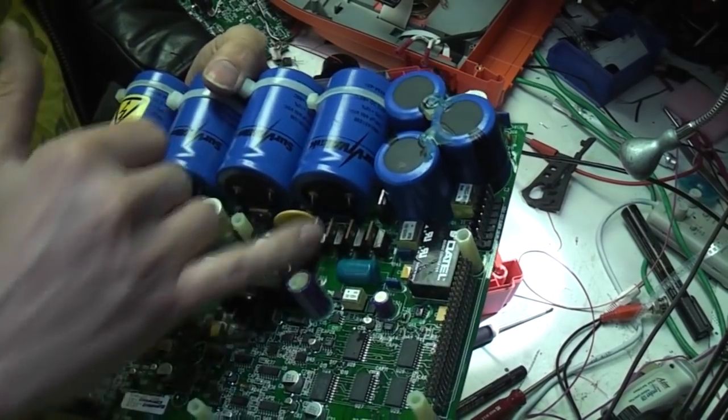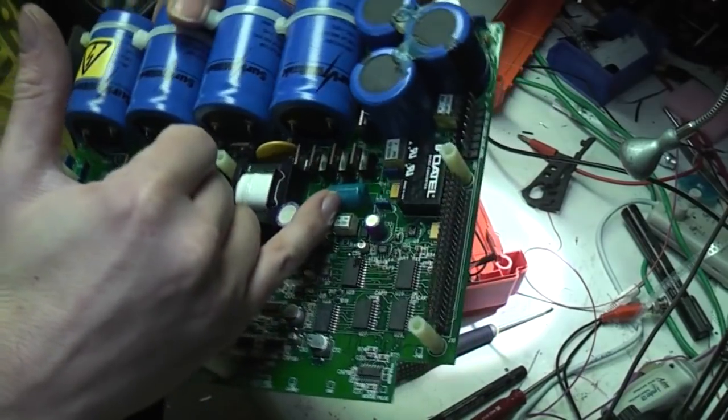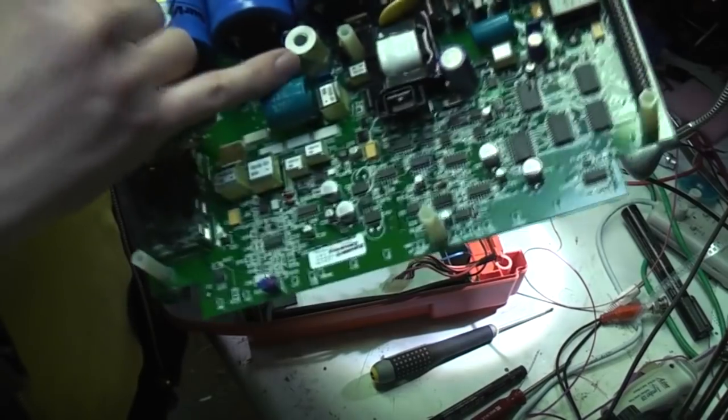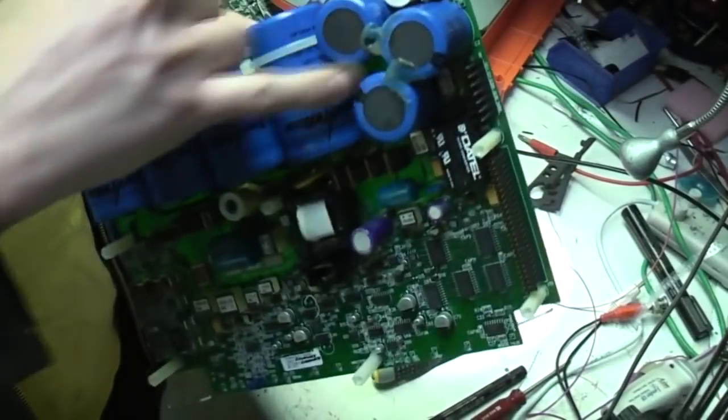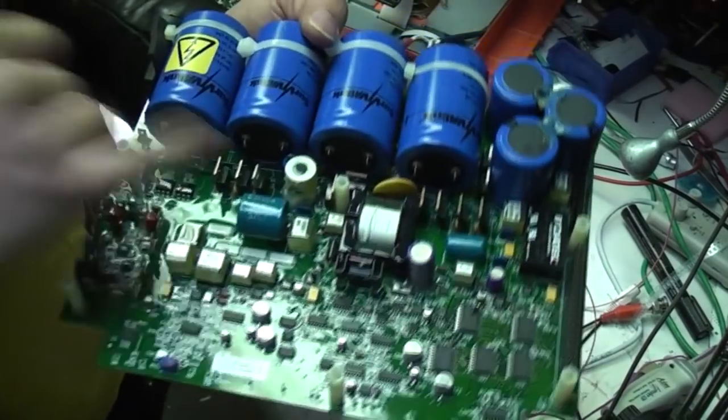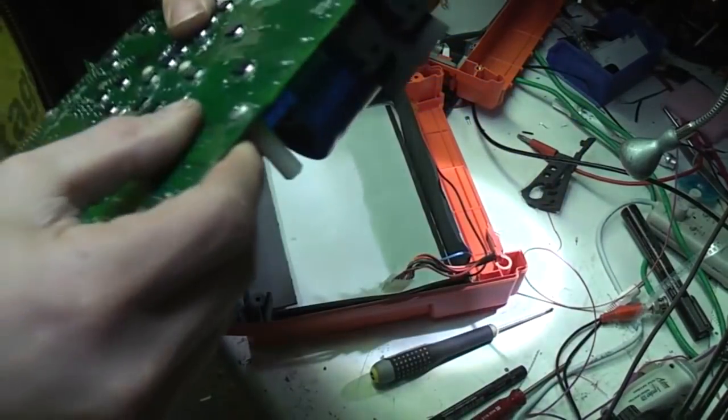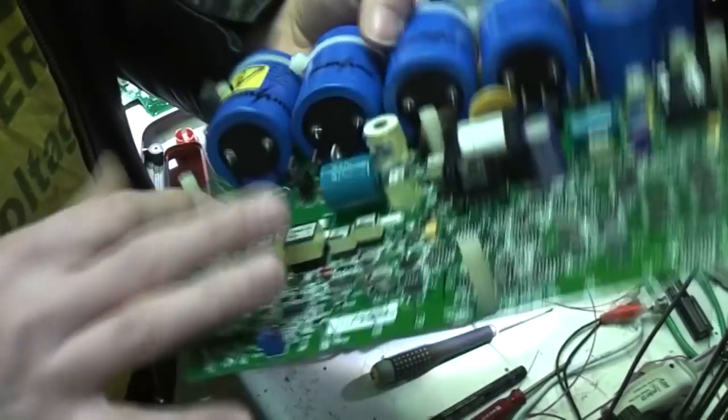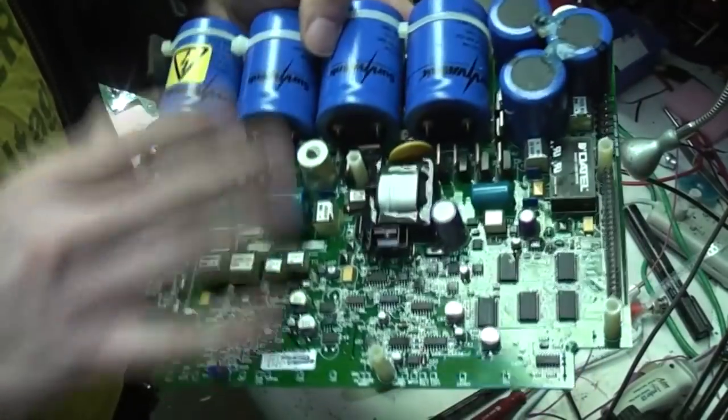Because if you look, there's quite a lot of duplication although you've got the one DC converter here. There's a lot of switching components. You've got another one of these big resistors which I suspect are for discharge testing. This inductor here, I'm guessing this may be for rise time control. Again there's a bunch of capacitors, one of these coils here and there's another one of these for this set of capacitors. So I'm just wondering if in fact this is almost two completely separate circuits it can either deliver a higher or low energy.